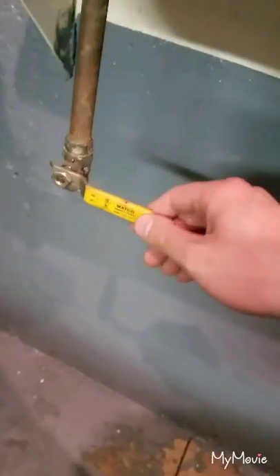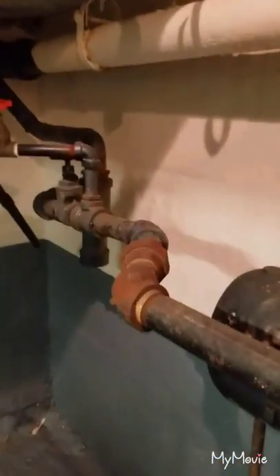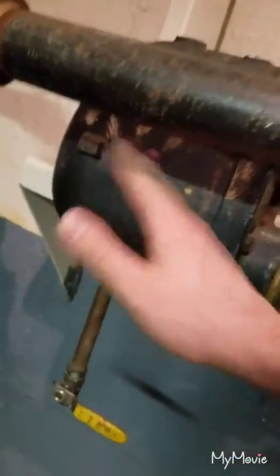I think we have vacuum. Well, that's the condensate coming back. So we know we have condensate coming back. Again, that's the condensate right there, all with the steam trap. Okay. You open this guy here, you'll get a mixture of flash steam and condensate. See, we have condensate and we have steam.